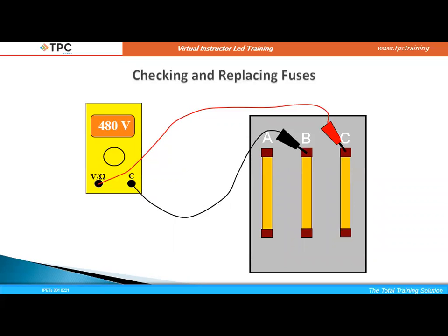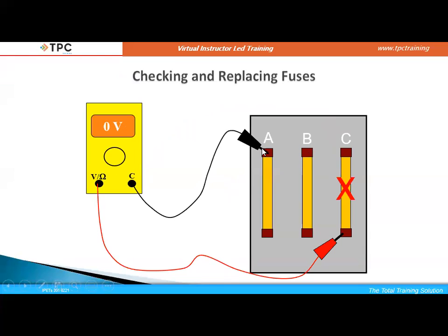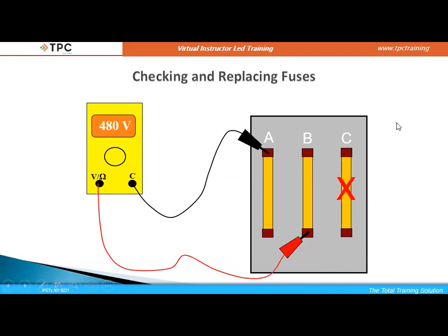Remember, I called this the crisscross method, which means I am going to take one lead and put it at the bottom of an opposite fuse. I put one lead on the line side of A, I take the other lead on the load side of C, and I don't see 480 anymore. Well, what does that mean? That means that this fuse is open. It's not allowing that 480 to make its way to the bottom of that fuse, and I now have found my defective fuse.